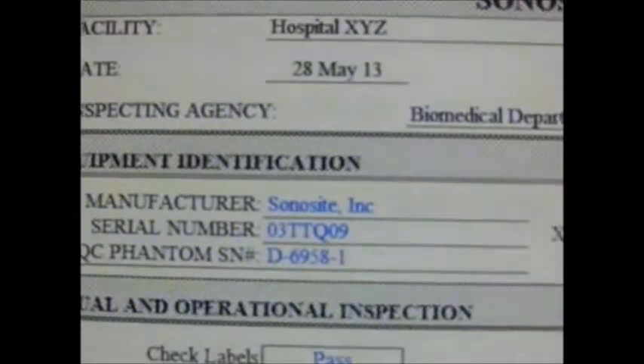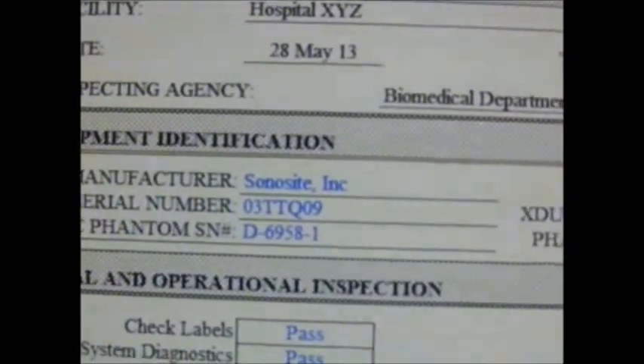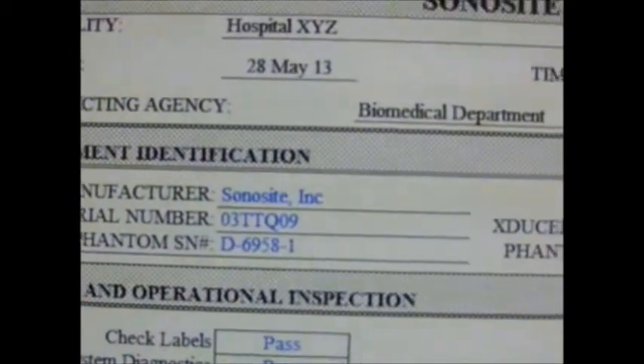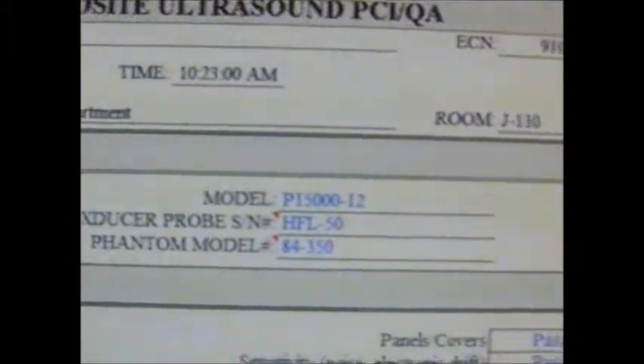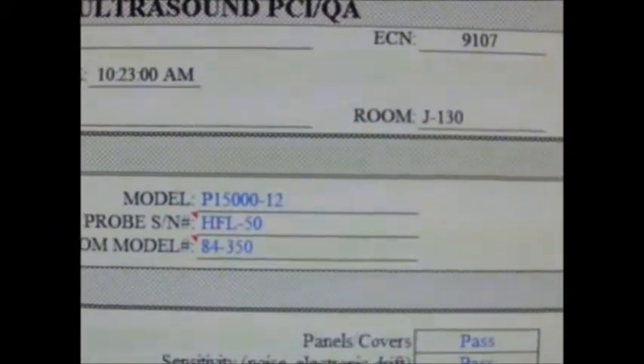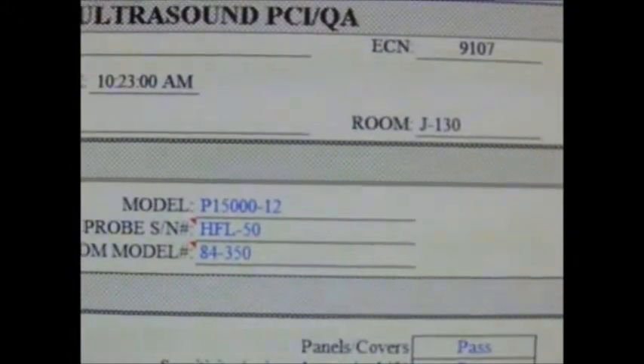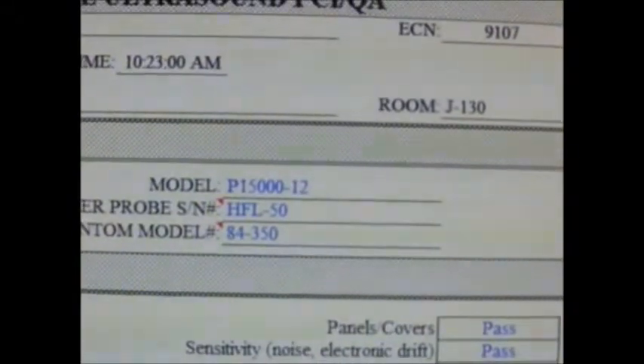In the far corner we have the facility name, which is Hospital XYZ, today's date, inspecting agency, which is the biomed department, the ECN or equipment control number or index number or asset tag, as well as the equipment room number.